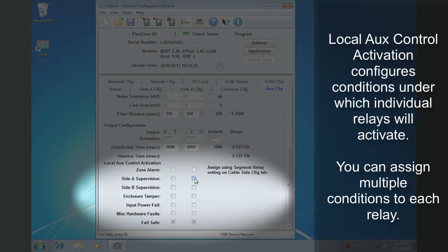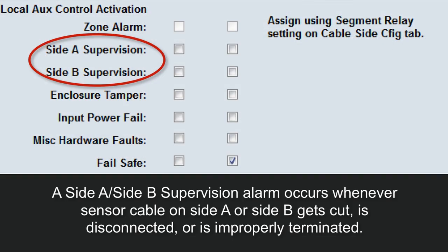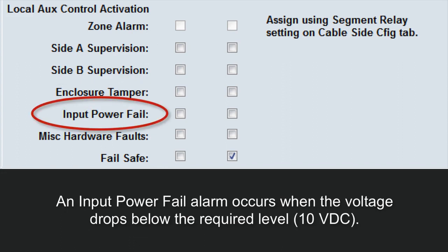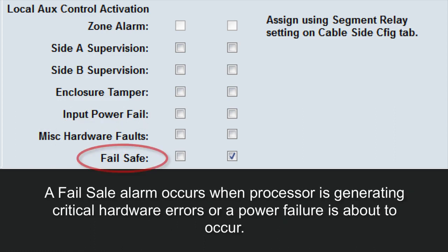Configure the conditions under which the individual relays will activate. You can assign multiple conditions to each relay. A cable supervision alarm occurs when the sensor cable on side A or side B gets cut, is disconnected from the processor, or is not terminated correctly. An enclosure tamper occurs whenever the FlexZone processor is opened. An input power fail occurs when the processor's voltage drops below the required level. Miscellaneous hardware faults occur when the processor is generating diagnostic alarms. Failsafe alarms occur when the processor is generating critical hardware errors or a power failure is about to occur.